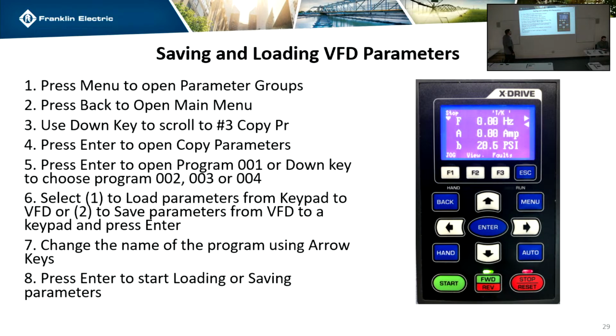So if you want to load the parameters, if you hit the menu button, it'll take you into the initial menu, and then you hit back. It'll go into the main menu of the drive itself. You go down to copy parameters, and if you hit enter, you'll see that I've got some random ones set in there. When you go in here, I don't want you to load anything right now because it's just going to mess up how we have it set up. But not only does it have different sections, I think it's 7 of them that you can save, but you can name them. So you can have it named as default or something, and then take the keypad from drive to drive to drive and load it up, and you know that that's your base programming.